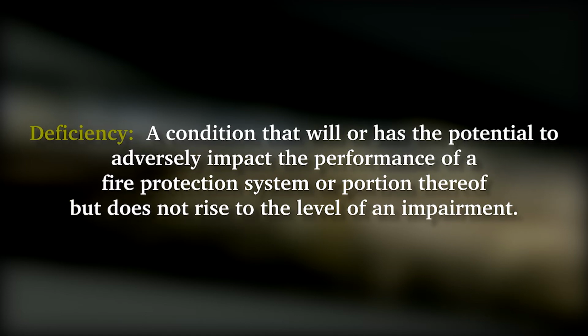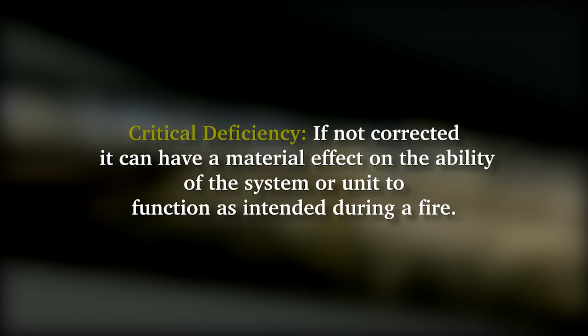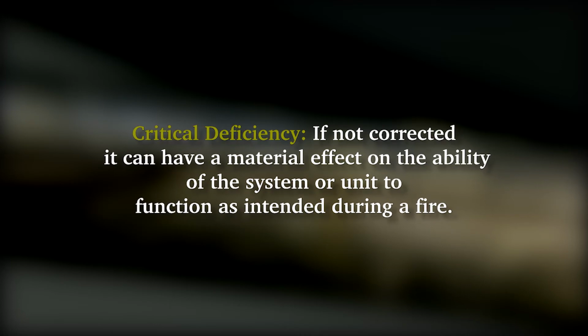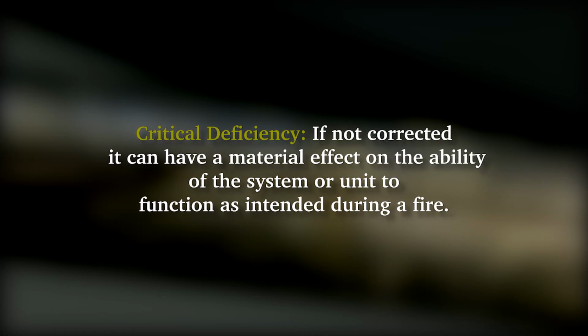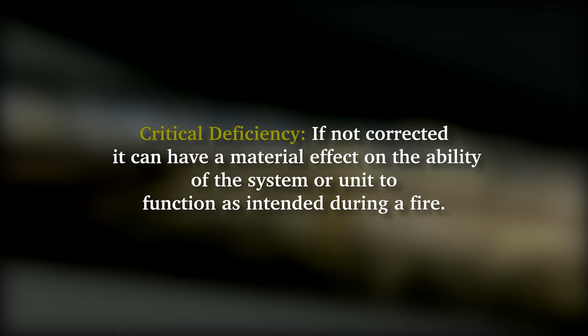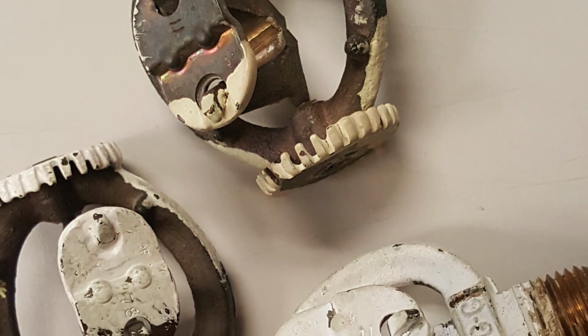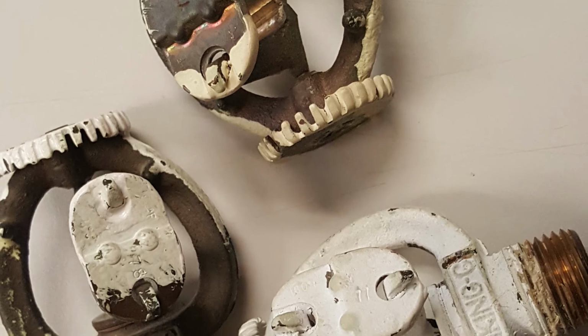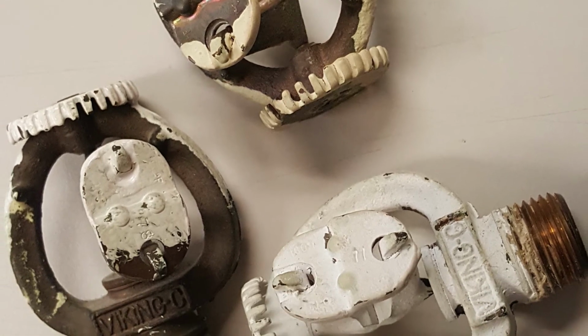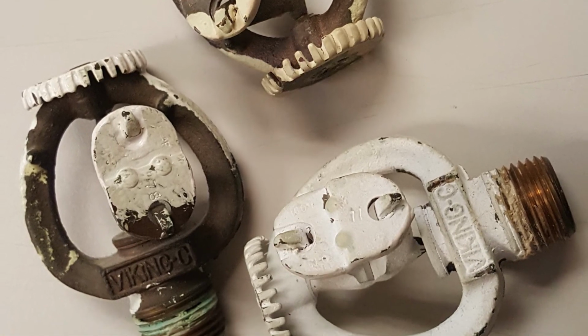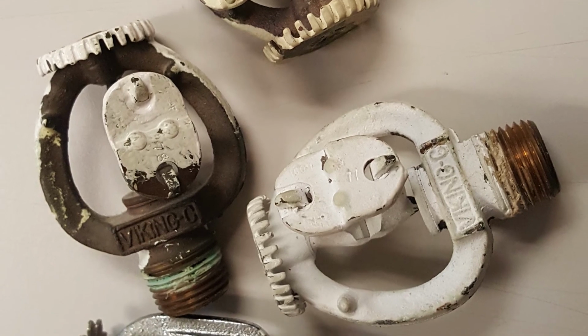There are two types of deficiencies. A critical deficiency can have a material effect on the ability of the system or unit to function as intended during a fire if it is not corrected. A fire sprinkler that is corroded or has been painted over would be considered a critical deficiency. Its spray pattern could be adversely affected, or it may not even work properly in the event of a fire.